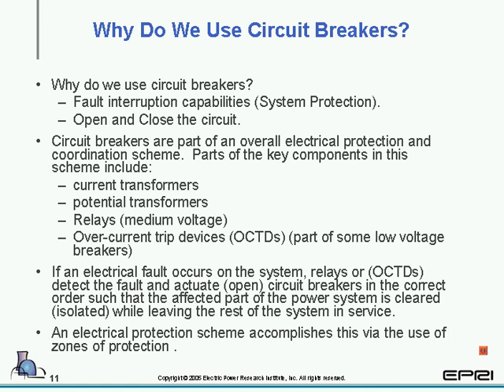Why do we use circuit breakers? Two major reasons we use circuit breakers are fault interruption capabilities and the ability to open and close the circuit. Circuit breakers are part of the overall protection. Some of the key components are the current transformers, the potential transformers, and relays, which are typically found in medium voltage switchgear, and overcurrent trip devices, which are normally found in low voltage gear. If an electrical fault occurs in the system, the relay or overcurrent trip device detects the fault and actuates the circuit breaker in the correct order, such that the affected part of the power system is cleared while leaving the rest of the system in service.